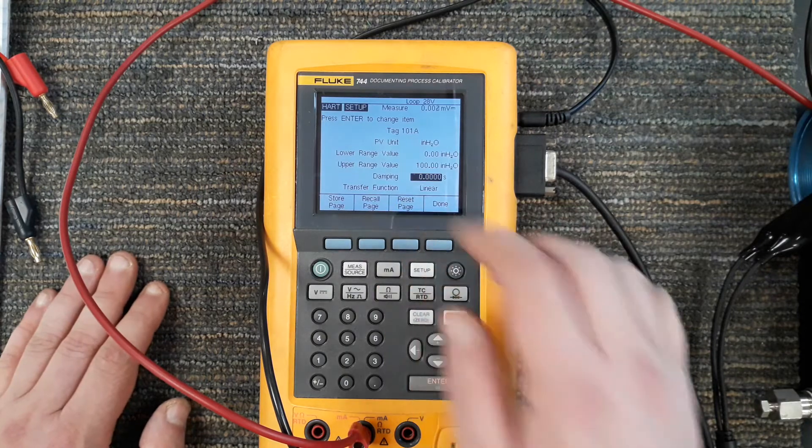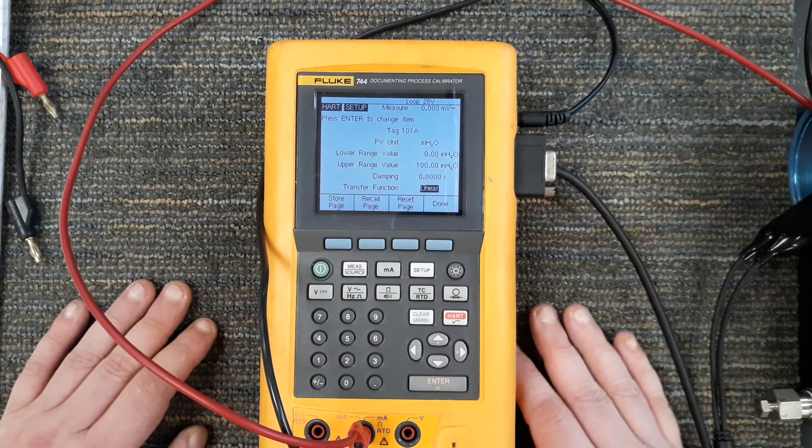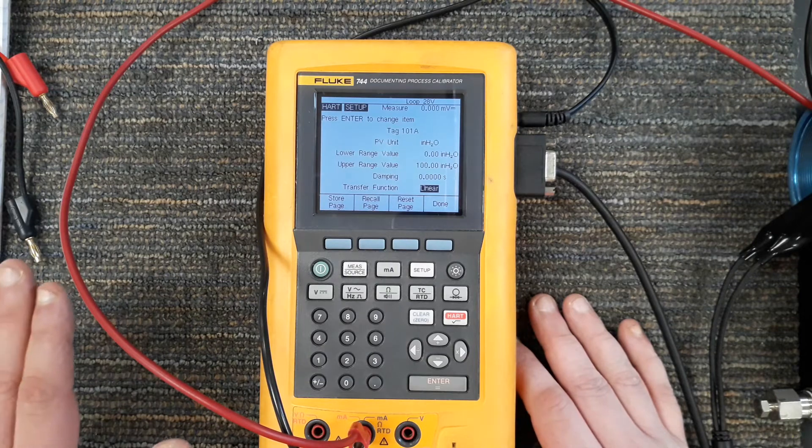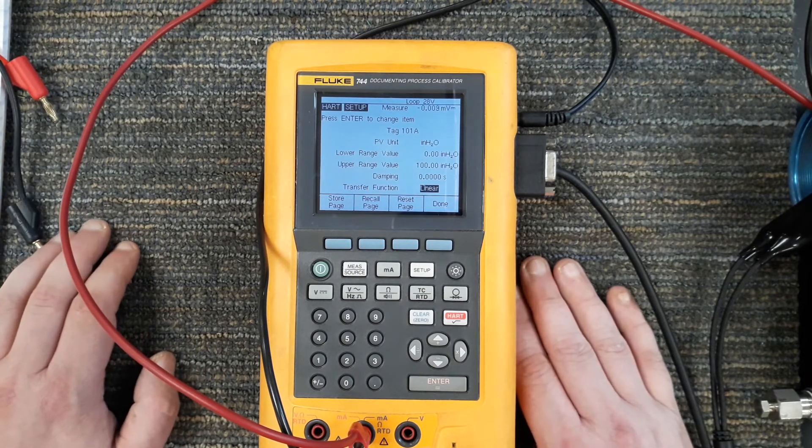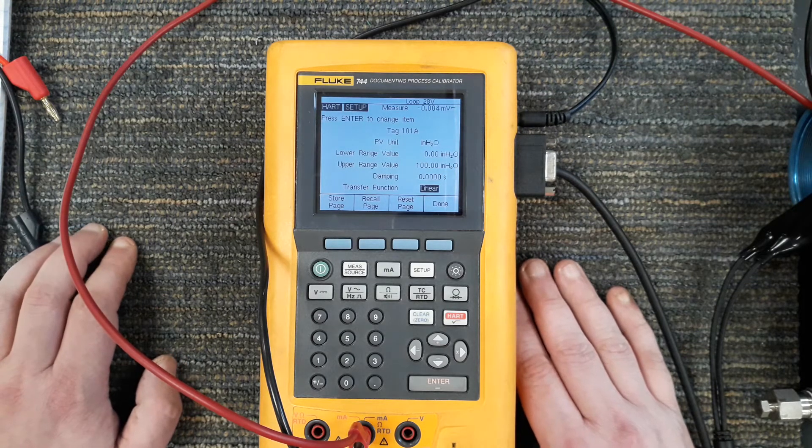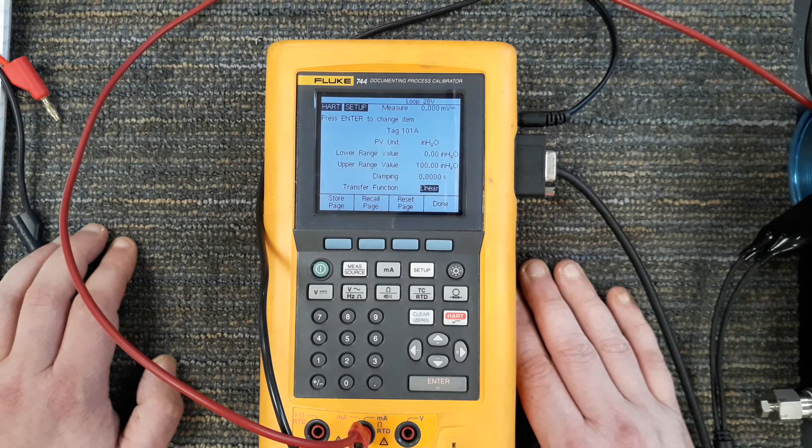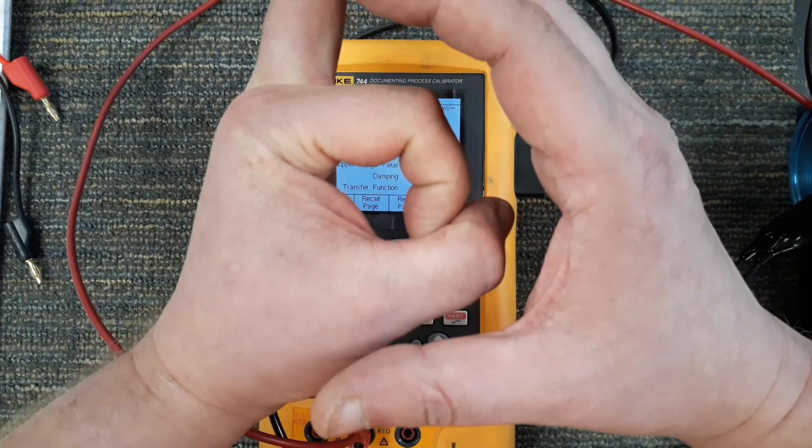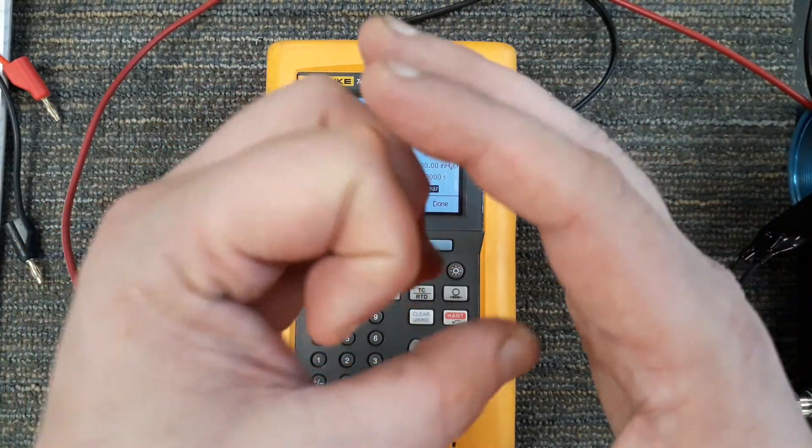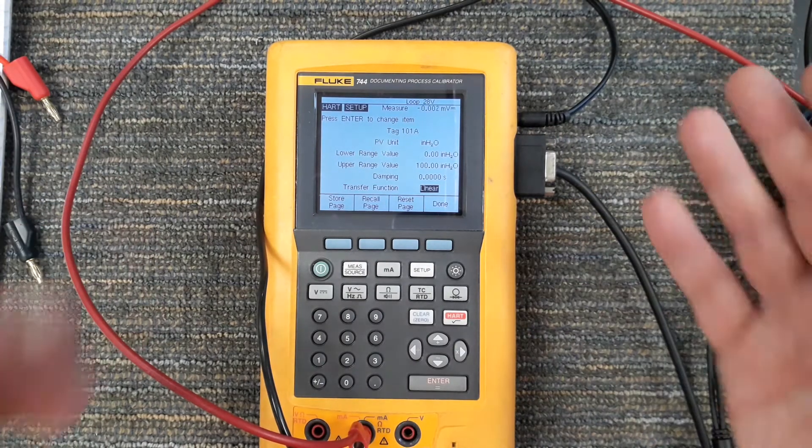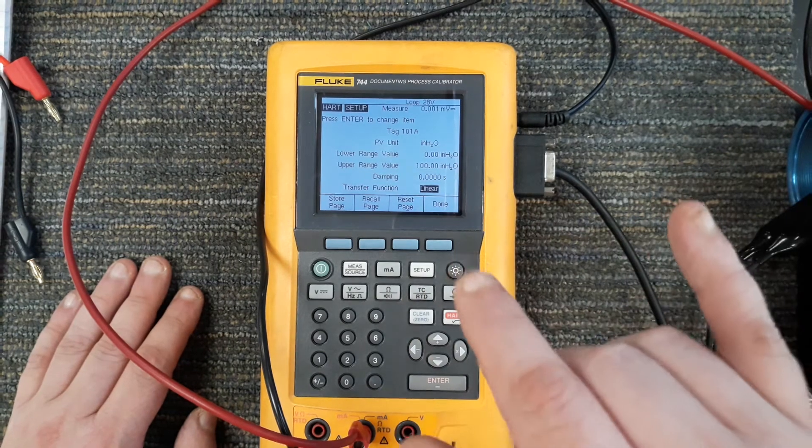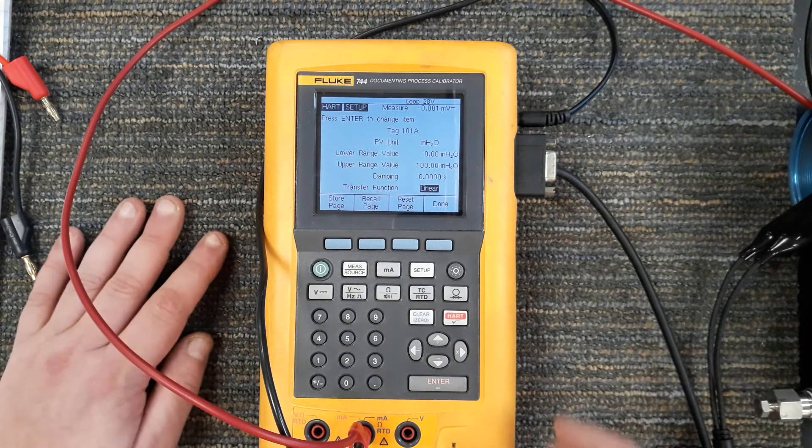Transfer function. This is more of a thing because this is a differential pressure transmitter. These can be used for a lot of things to include pressure readings, doing level calculations based on pressure readings, and then we can also calculate flow rates when this transmitter is used in conjunction with an orifice plate restriction which causes an increase in pressure on one side of the plate and a drop in pressure on the other. Think of it like a pipe, but then in the middle you have a hole and the rest is covered by plate. If you have a larger volume of liquid trying to squeeze into a small hole, the pressure going in is going to increase, and because all that is being pushed through a small hole and then allowed to expand back out, the pressure decreases. We get a high pressure on one side and a low pressure on the other, and we can actually measure the differential pressure across that plate.